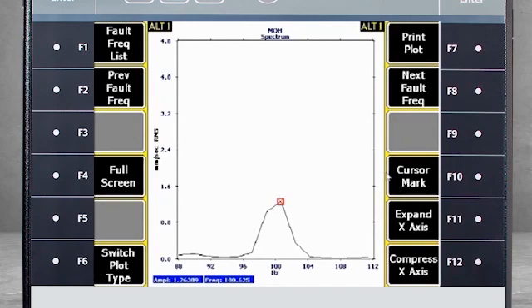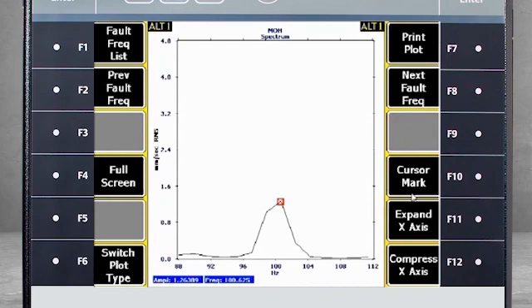The F10 cursor mark will use best fit curves to recalculate the analog peak using the digital information from the resolution lines. Note that when I click F10, the frequency and amplitude are recalculated to better fit the analog scenario.